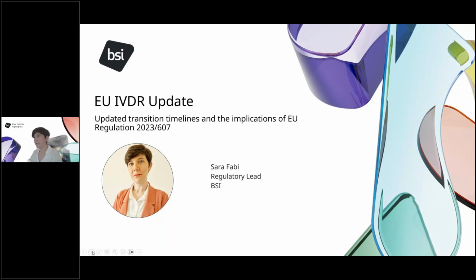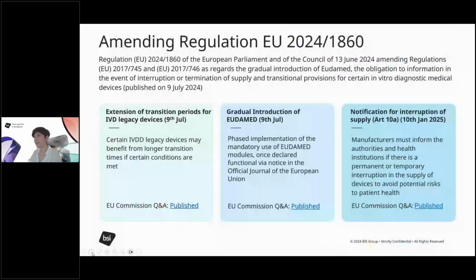I'm going to cover the most recent amending legislation. In line with the concern that led to the publication of the 607 amending regulation, last year on the 9th of July 2024, the amending regulation EU 2024/1860 was published, introducing 3 elements. The first is the extension of transition periods for IVD legacy devices, so certain IVDD legacy devices may benefit from longer transition times if certain conditions are met. Then the amending regulation allowed for a phased implementation of the mandatory use of EUDAMED modules once they are declared functional by a notice in the Official Journal of the European Union.